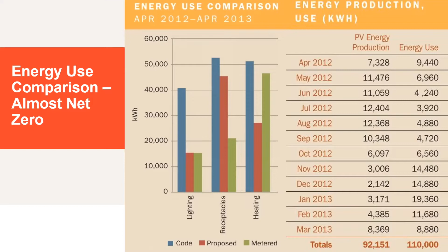They're getting there now. When you start doing that on a net zero building, you find they didn't have individual metering on all the circuits - this is ten years ago. How can you start tweaking and making sure things are set up correctly if you don't have individualized metering? So part of the project during recommissioning was putting additional electric meters on all the mechanical systems, individually by branch, so we could really track down why we were missing targets. Because if you don't have the data, you can't do the analysis side - or not as well - you start having a lot of asterisks.